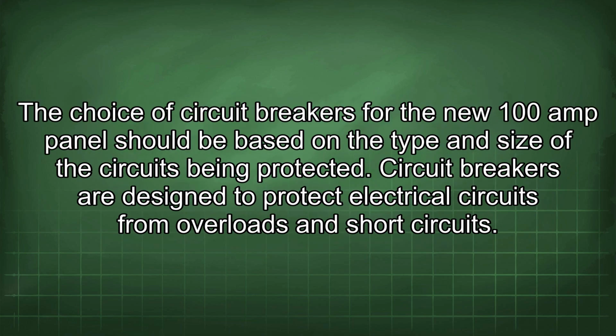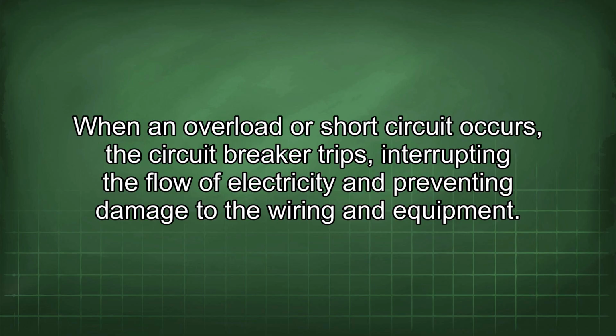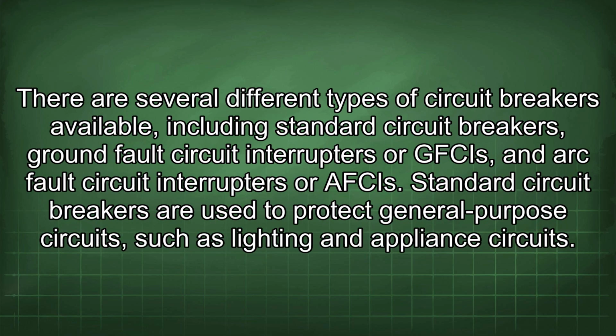The choice of circuit breakers for the new 100 amp panel should be based on the type and size of the circuits being protected. Circuit breakers are designed to protect electrical circuits from overloads and short circuits. When an overload or short circuit occurs, the circuit breaker trips, interrupting the flow of electricity and preventing damage to the wiring and equipment. There are several different types of circuit breakers available, including standard circuit breakers, ground fault circuit interrupters or GFCIs, and arc fault circuit interrupters or AFCIs.